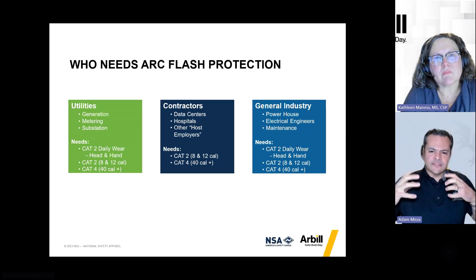Cat 2, Cat 4, and you can go beyond 40 cal as well on some data centers, hospitals, older buildings. General industry, that's your manufacturers of the world, right? Those folks are usually doing an incident energy analysis, like arc flash studies. So they know this panel is going to produce this amount of incident energy if anything ever happens. This panel does X, that does X, and they'll have a report that safety leaders can use to properly outfit folks. Usually they're in a uniform program, and they'll don 40 or higher calorie gear, depending on the need at the plant.